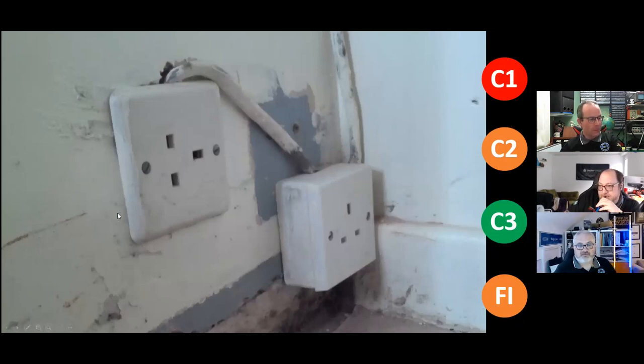Where, from what it looks like, someone has spurred off a socket which is sideways to add another socket, and then they've spurred off of that. So where would you start with this? How would you look at this as far as a codable observation? Lack of mechanical protection on the cabling, possible strain on the conductors in the back. Well, yeah, the method isn't technically sound.